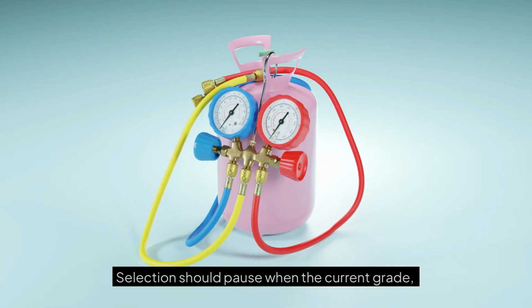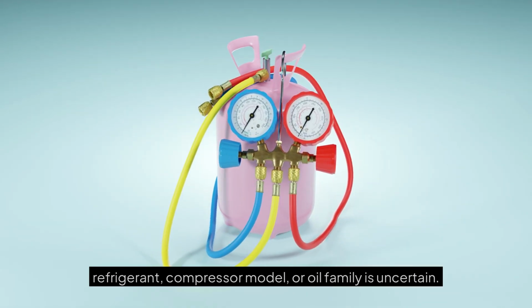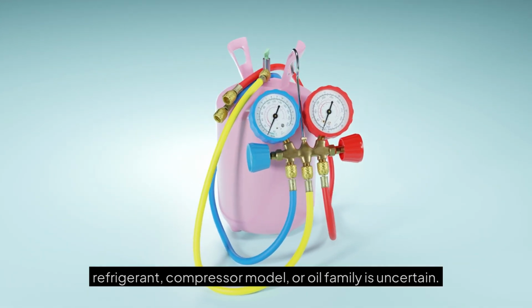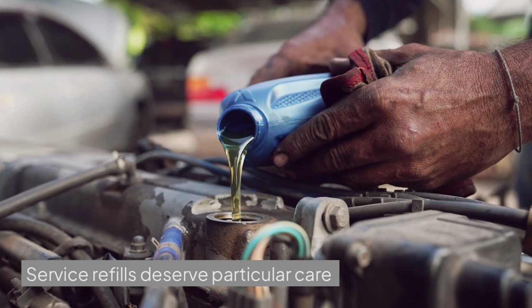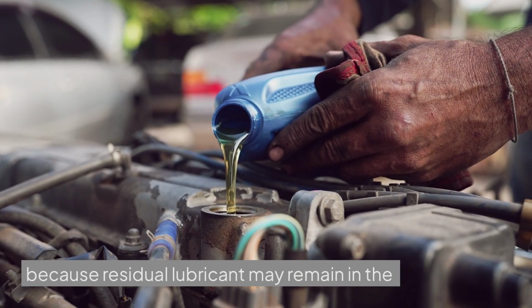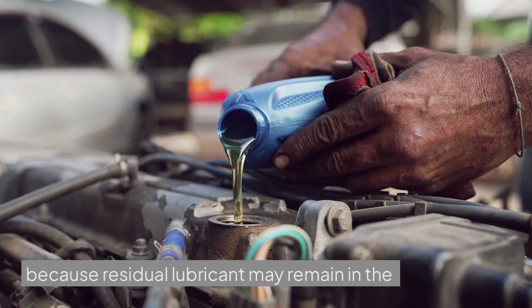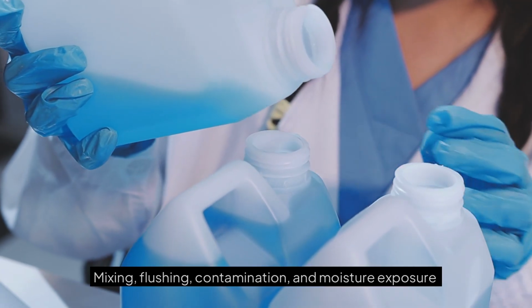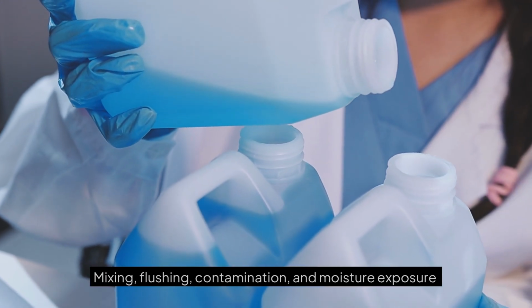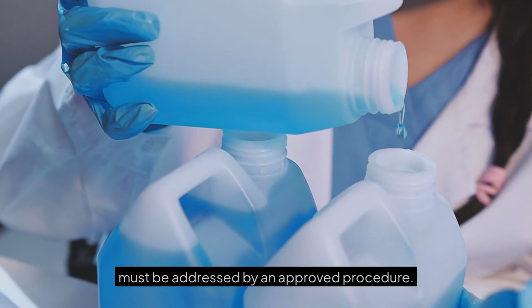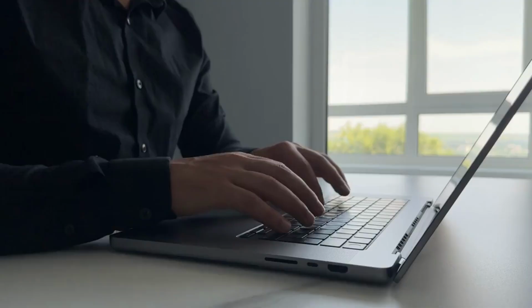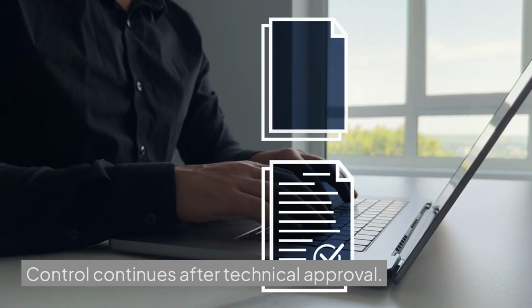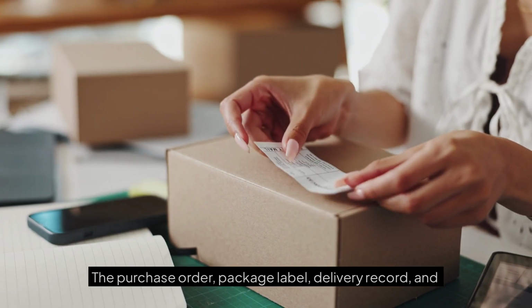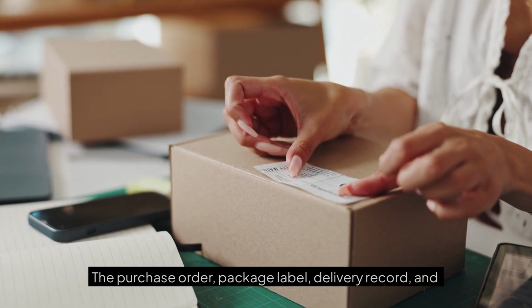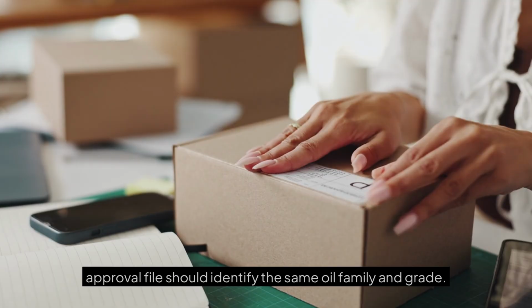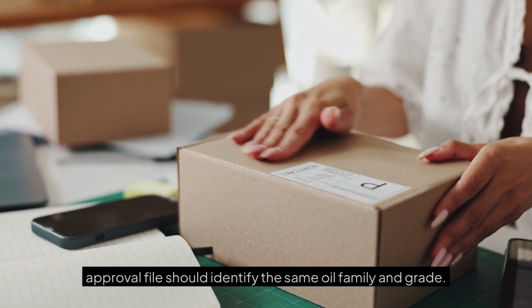Selection should pause when the current grade, refrigerant, compressor model, or oil family is uncertain. Service refills deserve particular care because residual lubricant may remain in the circuit. Mixing, flushing, contamination, and moisture exposure must be addressed by an approved procedure. Control continues after technical approval. The purchase order, package label, delivery record, and approval file should identify the same oil family and grade.